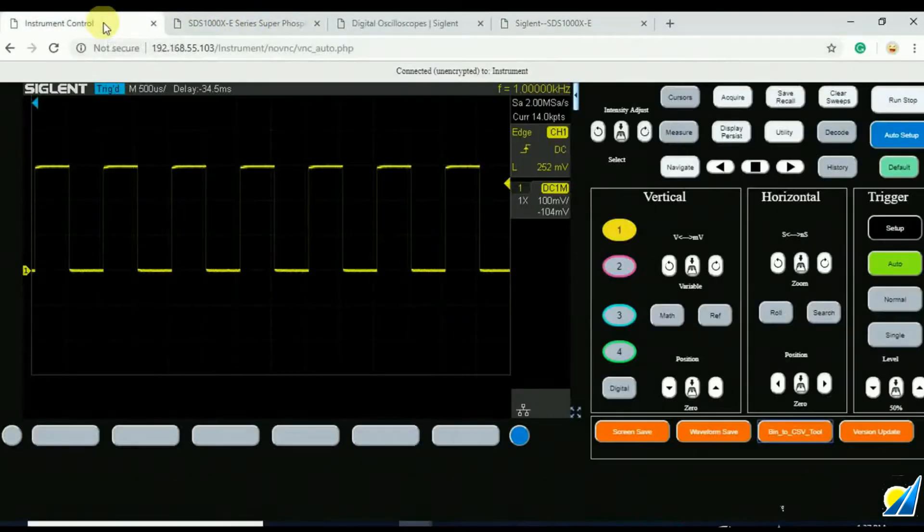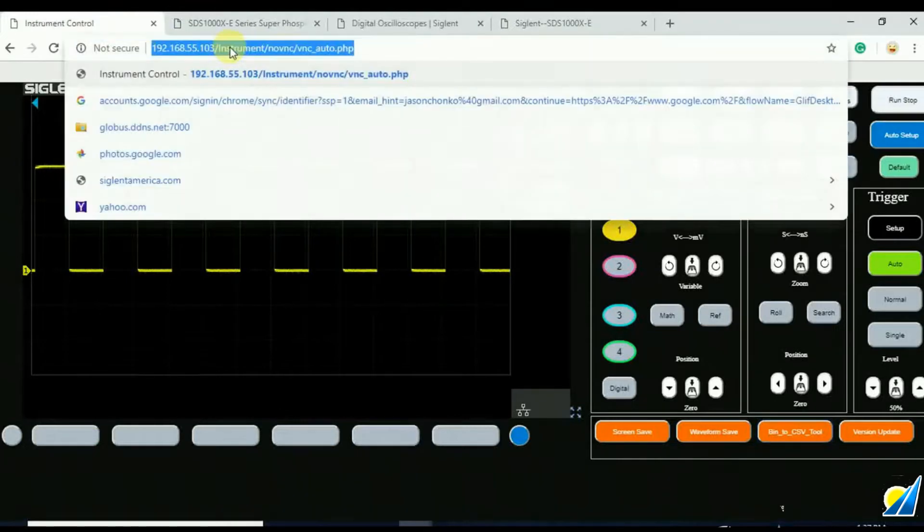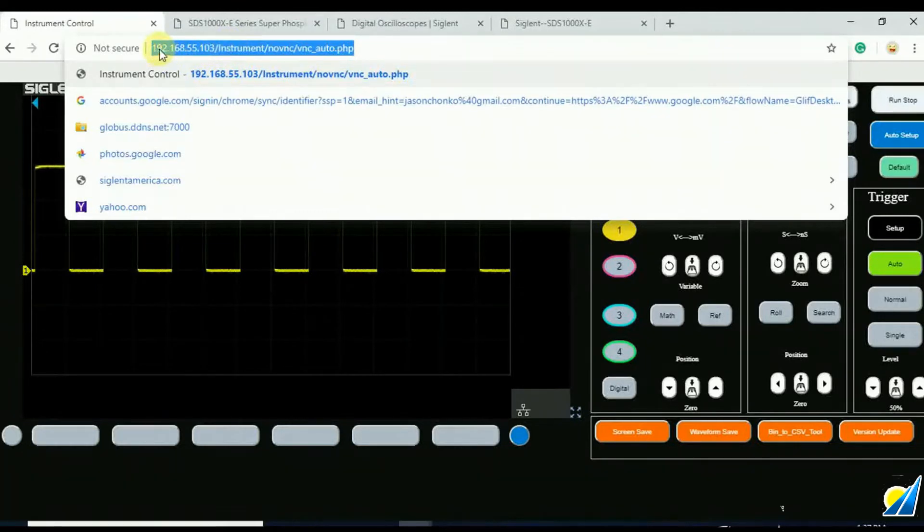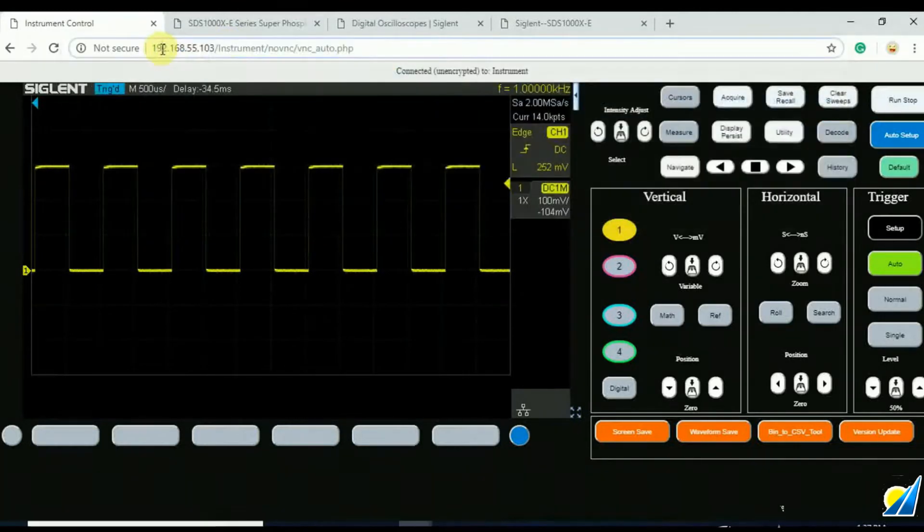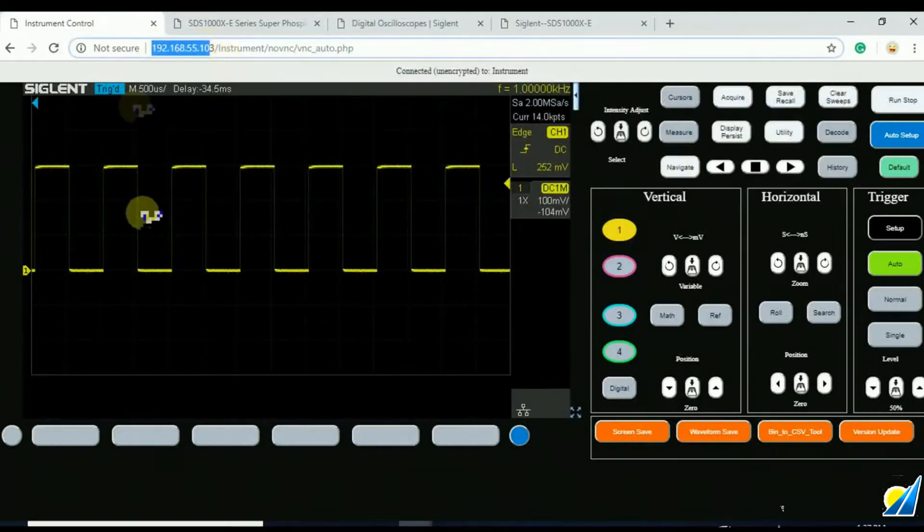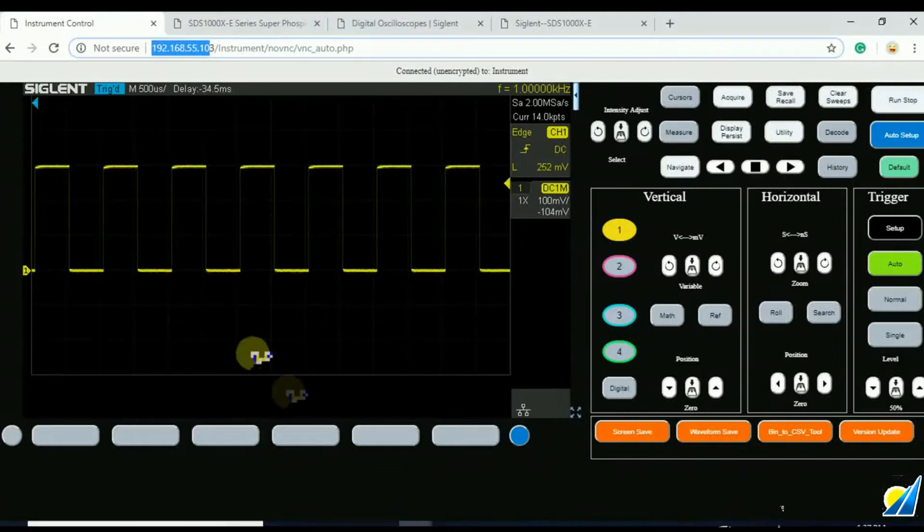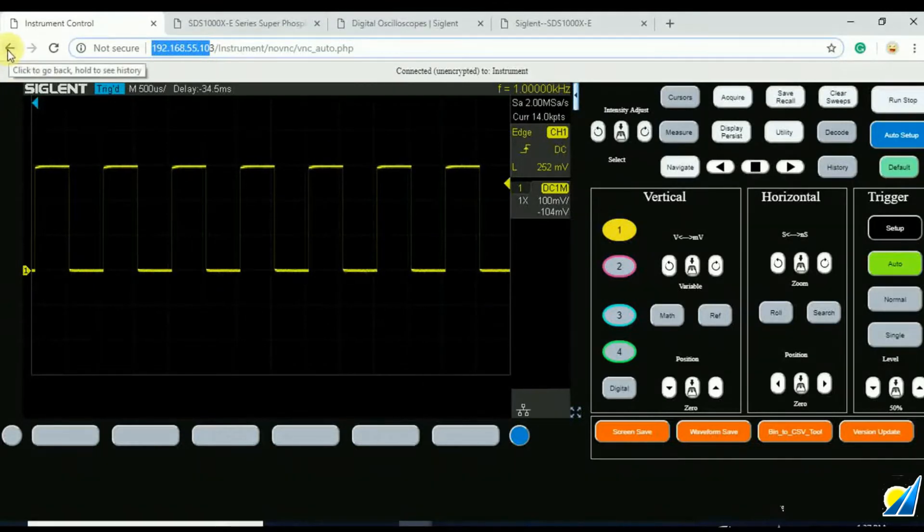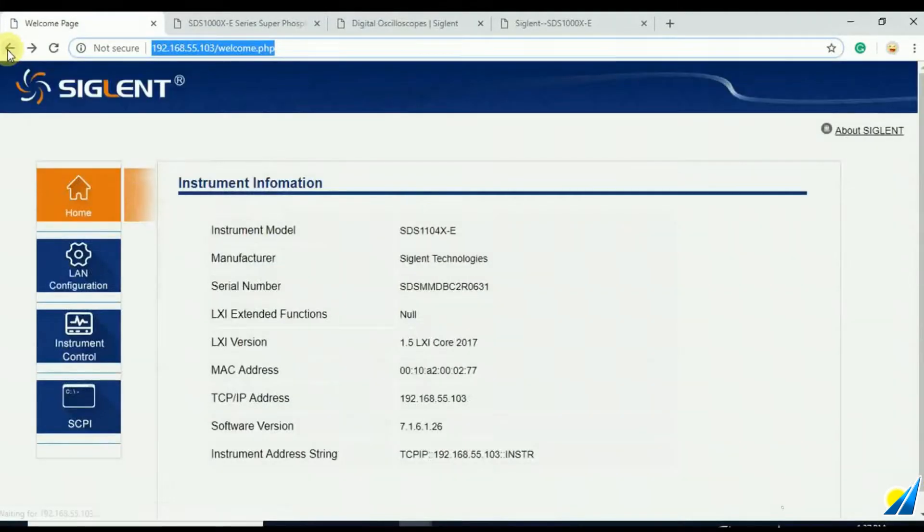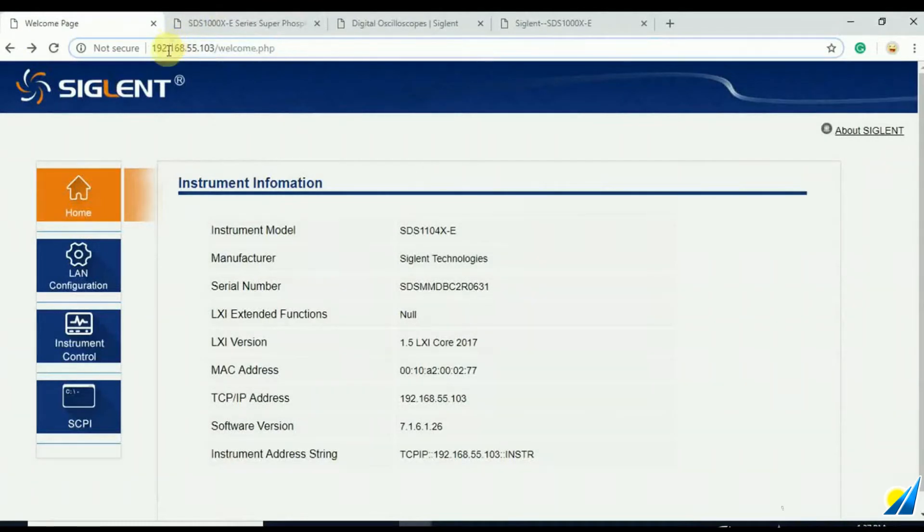Over to the device under test here. I have previously connected an oscilloscope, a 4-channel X-E, to a local area network. I've typed in the IP address here and we've brought up the actual control panel. I'll just show you how that works briefly. Just go back to the welcome page, type in the IP address up here, hit enter and we come up with the home screen.